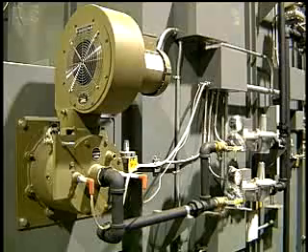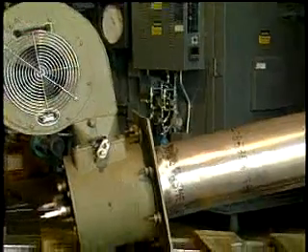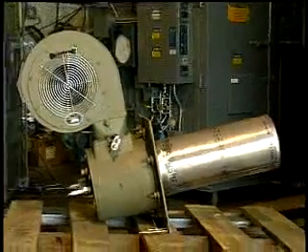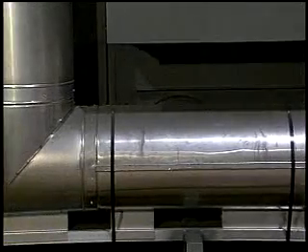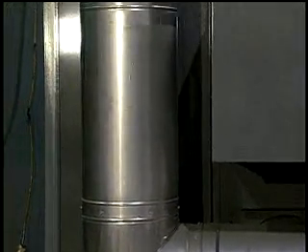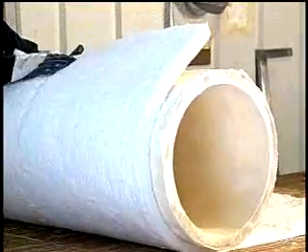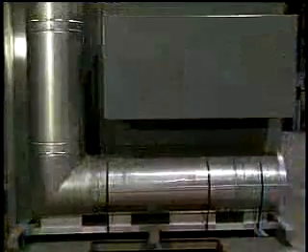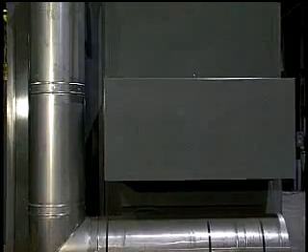Steelman burn-off ovens are designed to use an exterior multi-chamber burner system. The primary burner releases heat in the top of the oven, and the afterburner removes combustible material from the bottom. Both chambers are equipped with industrial burners constructed of high-grade cast iron — most competitors use sheet metal burners designed for incinerator duty. The afterburner and exhaust stack are constructed from a 36-inch long, one-piece vacuum-form ceramic fiber sleeve rated at 2,400 degrees Fahrenheit, wrapped with a 1-inch ceramic fiber blanket and inserted into a stainless steel shell. This stack is made in 3-foot sections, easily installed at the customer's facility. Special lengths and elbows are available; most competitors use 12-inch long sleeves with joints that often burn out.